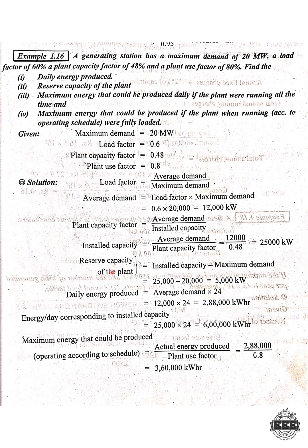Next, the reserve capacity of the plant. Reserve capacity equals installed capacity minus maximum demand. The installed capacity is 25,000 kilowatts and the maximum demand is 20,000 kilowatts. So 25,000 minus 20,000 equals 5,000 kilowatts. So the reserve capacity of the plant is 5,000 kilowatts.